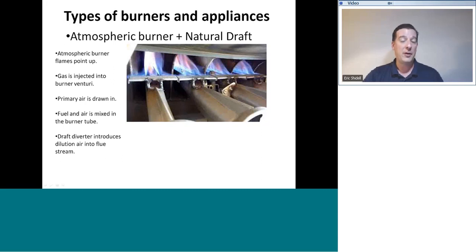That is the flame that we want to pay attention to. When there is a lot of combustion air, when the primary air is too intense, there's too much of it being drawn in, those flames will be very, very tiny. They will be maybe 3/16 to a quarter of an inch tall. They will be very sharp and well-defined and very tight.